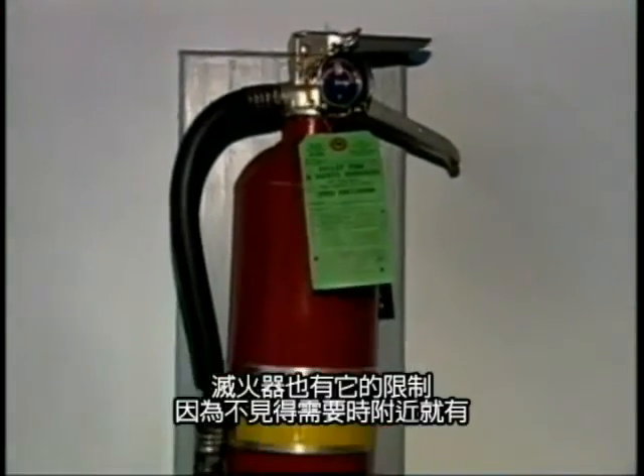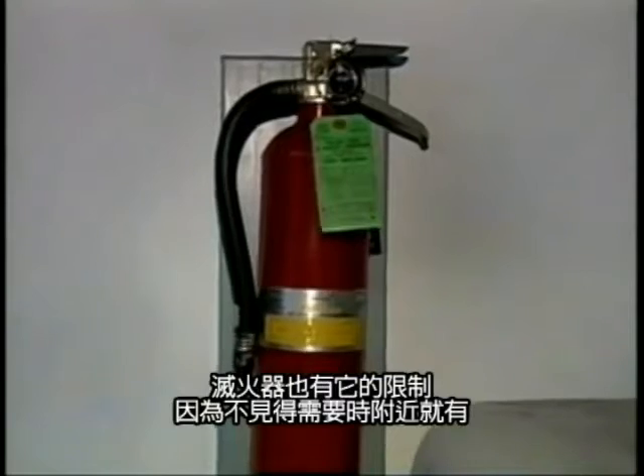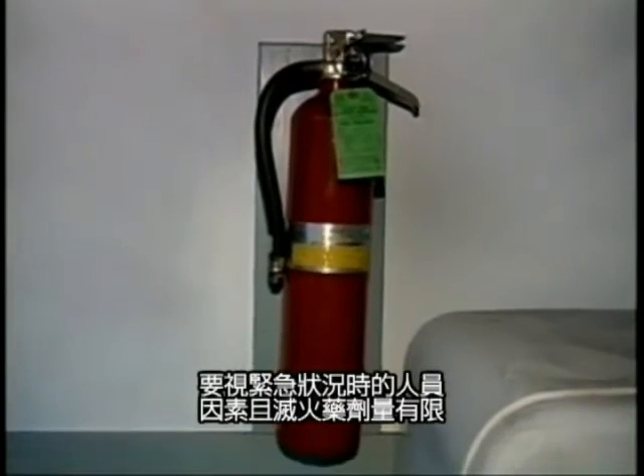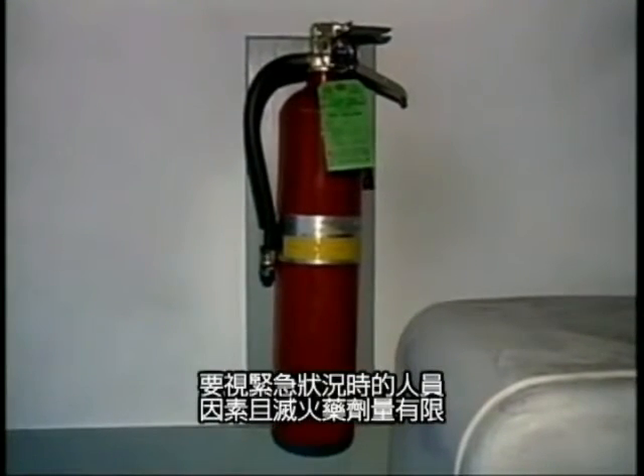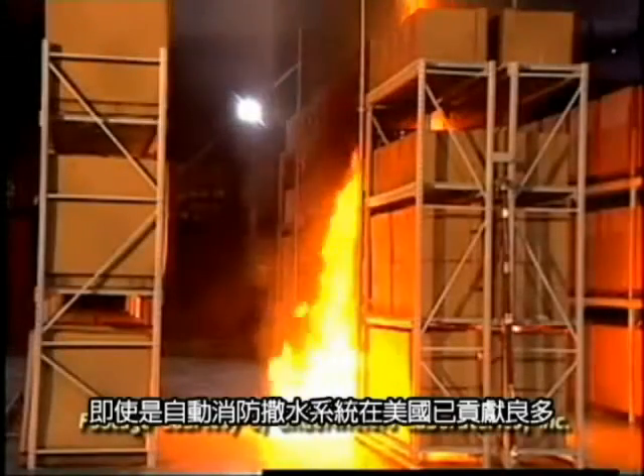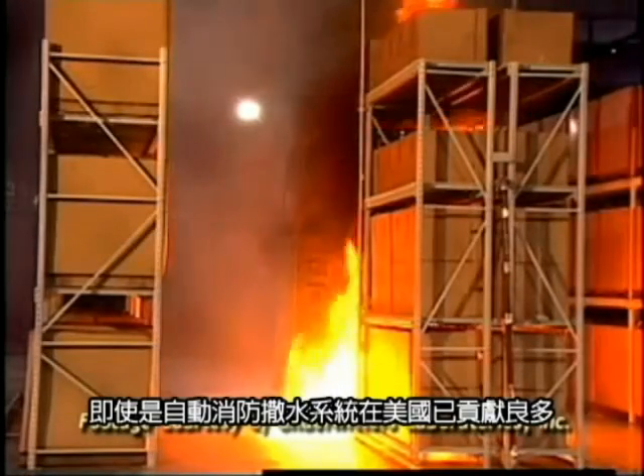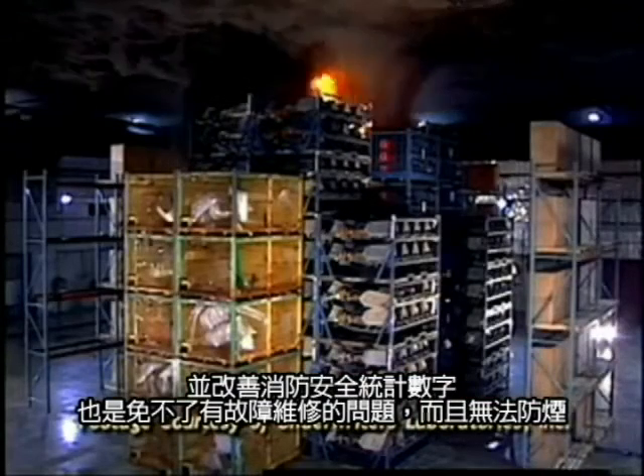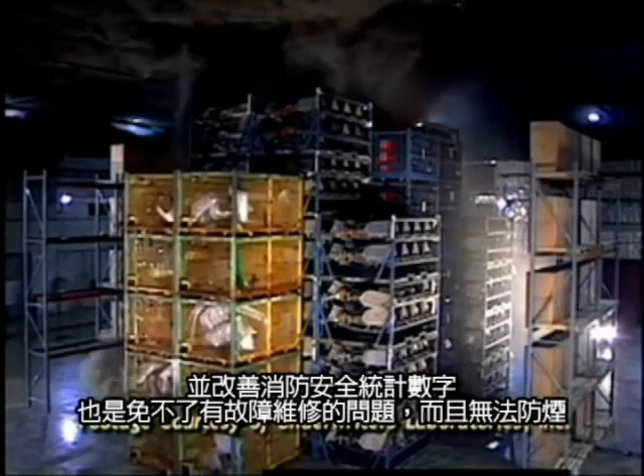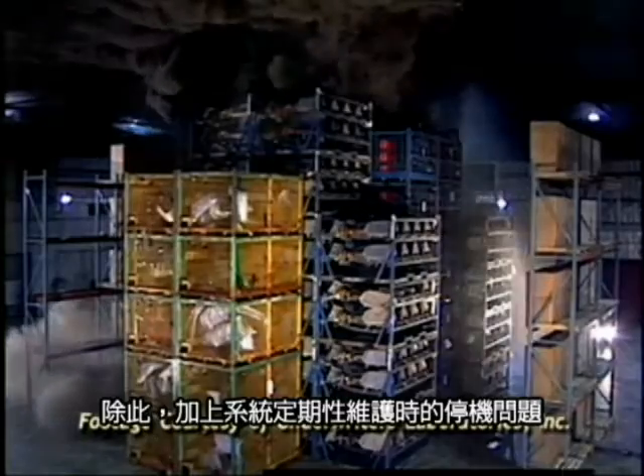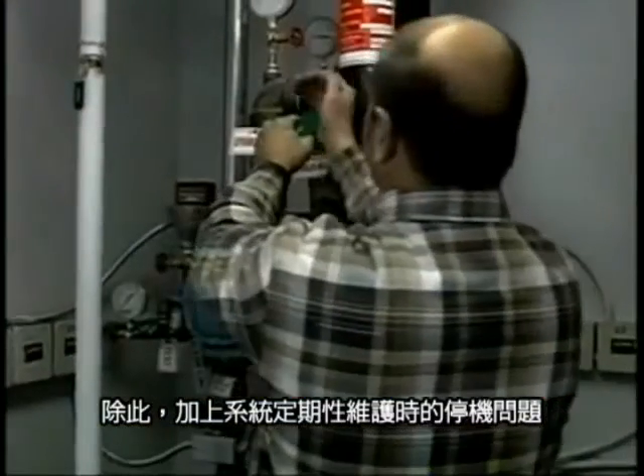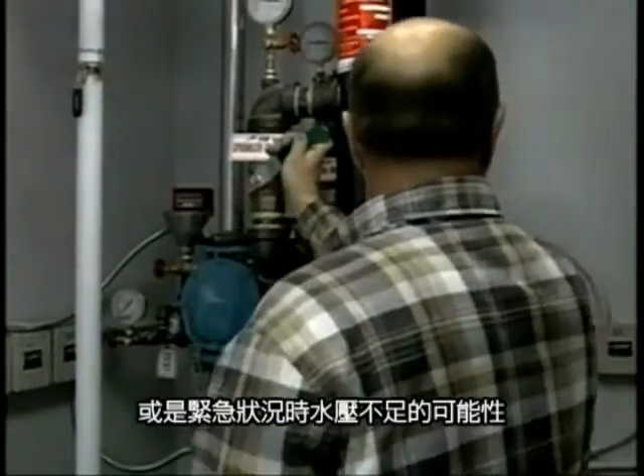Extinguishers also have limitations, as they're not always located where they're needed, depend on a human element during an emergency, and have a limited supply of agent. Even automatic sprinkler systems, which have done much to improve the fire safety statistics in this country, are susceptible to impairment and do little to stop smoke. Add to this the periodic downtime for system maintenance or the potential during an emergency for inadequate water pressure, and it becomes obvious that sprinklers are only one part of a complete fire protection plan.